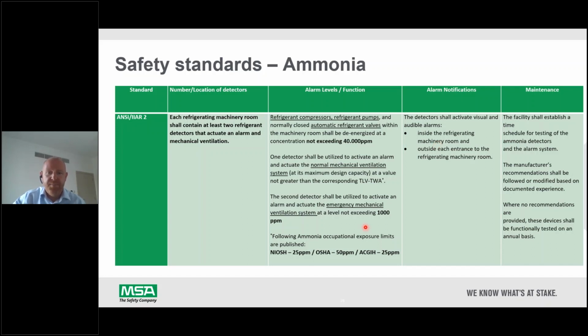And then we have the occupational exposure limits to ammonia. Where you have people working in a food processing plant that's using a direct expansion or a flooded ammonia system, you need detection levels down to 25 ppm where those people are working. Ammonia has an inbuilt warning in the smell of it, and so does propane and some of the other gases, so you will know it's there. But the HFCs don't have this smell added to them, so that's why sometimes they can be more dangerous.